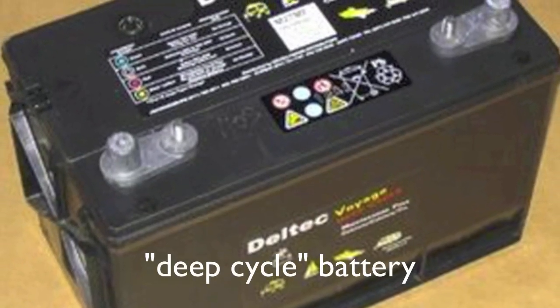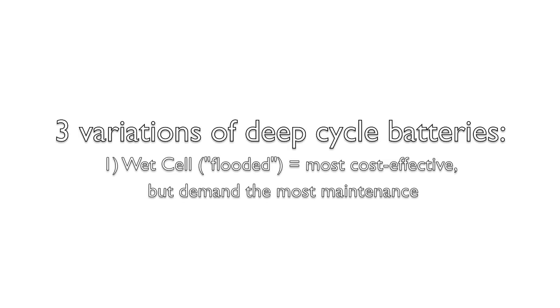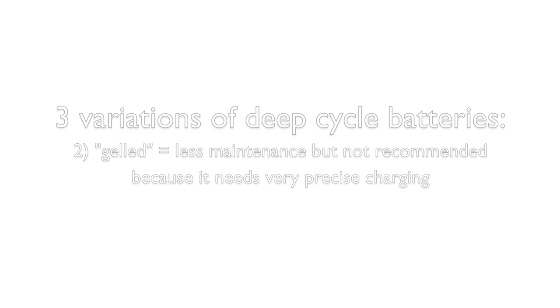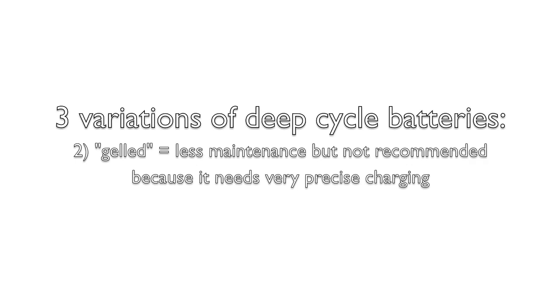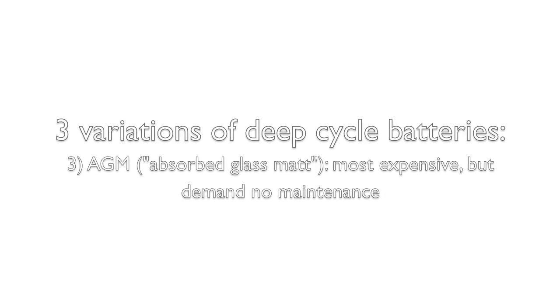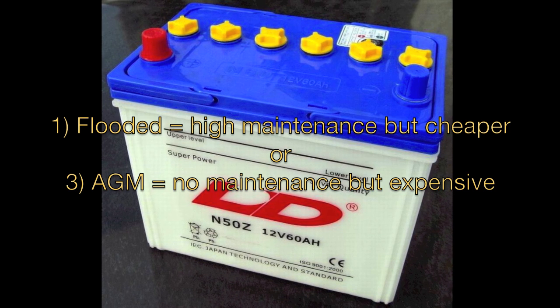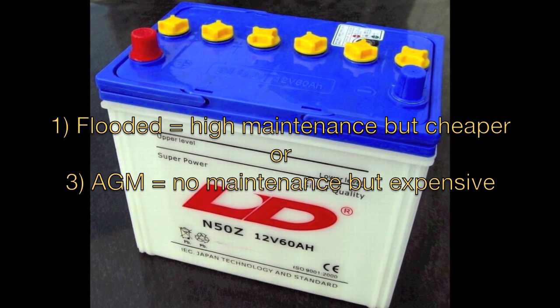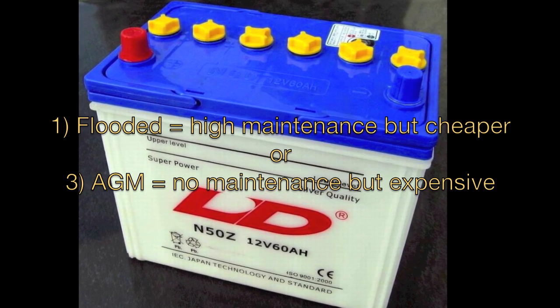When we're talking about batteries, we're talking about deep cycle batteries. And these are also called forklift batteries or golf cart batteries. Now there are three variations of deep cycle. The first is wet cell. They're the most cost effective, but they demand the most maintenance, which we'll talk about. Gelled are just too touchy. They're not recommended. Most people don't. AGM, most expensive, but they demand no maintenance whatsoever. So here are your two choices: flooded, high maintenance but cheaper; AGM, no maintenance but expensive.